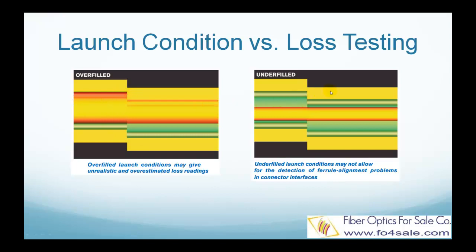Now let's see what happens if the launch condition is too much underfilled, as shown in the second picture. If the launch condition is too restrictive, only very few lower order modes near the center of the core are excited. So the light beam passes through the misaligned connectors with very low loss, probably 0.2 dB. Again, this gives a misleading loss, which is underestimated.